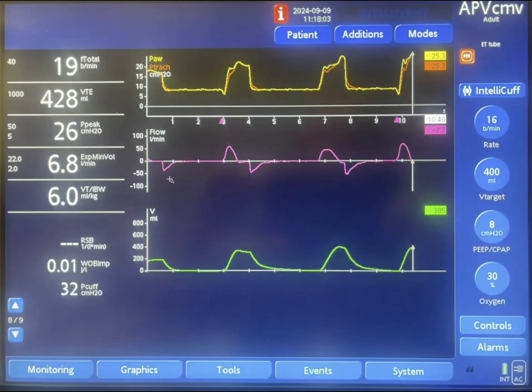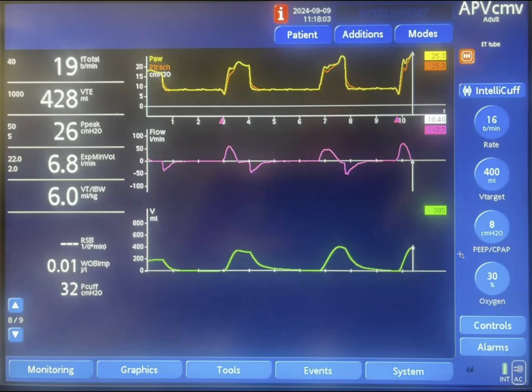Cycling in mechanical ventilation indicates changing from inspiration to expiration. You can set the inspiratory time by setting the IE ratio and the respiratory rate. On some ventilators like Draeger, you can directly set the inspiratory time on the machine.